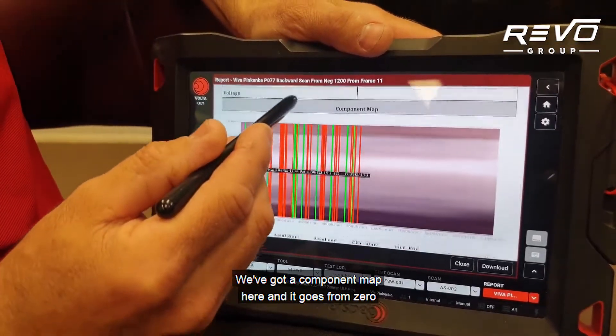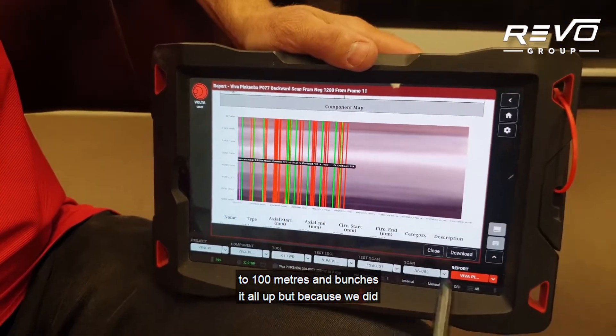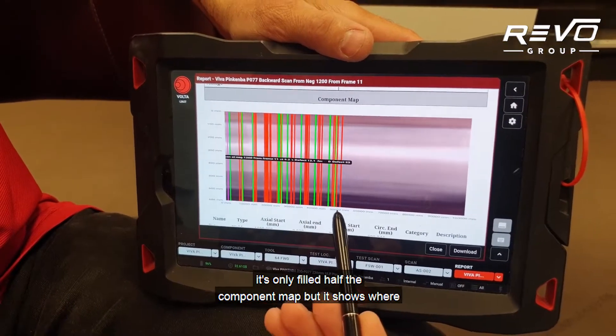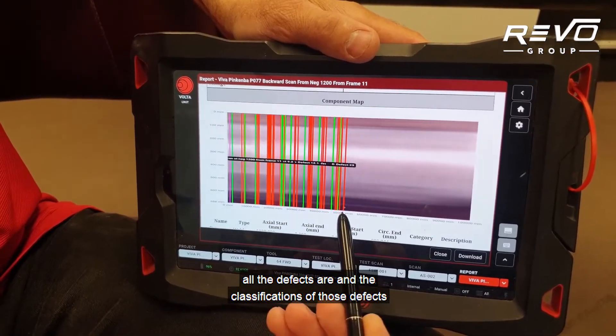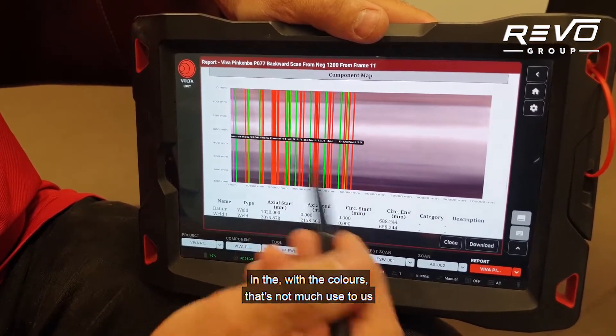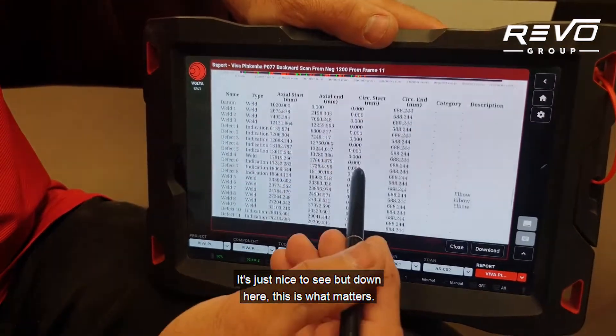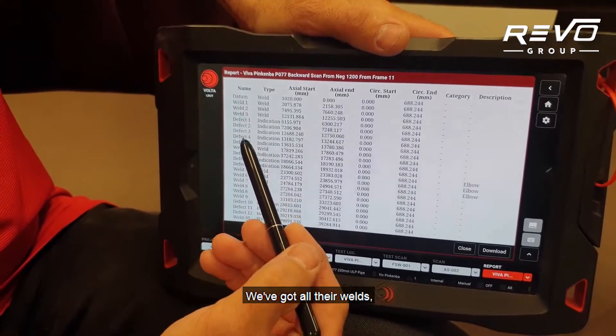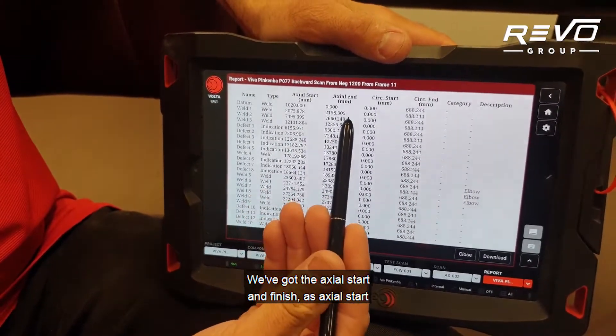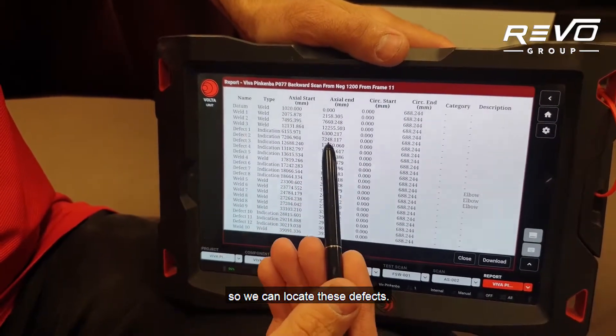That's quite comprehensive. We've got a component map here that goes from zero to 100 metres. Because we did a backward scan in one direction — not a bi-directional scan — it's only filled half the component map, but it shows where all the defects are and their classifications by colour. Down here is what really matters: we've got all our welds and defects numbered and labelled, with axial start and finish positions in millimetres so we can locate these defects precisely.